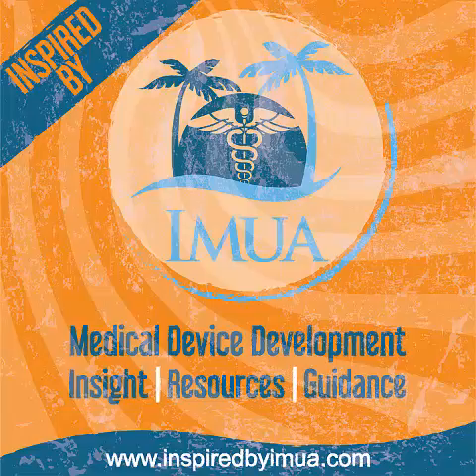So you might take some of the prototypes out to the field and get clinician feedback, right? How do they think it works? And then in a testing laboratory, how does this package perform when you put it through some hazards and stresses? Temperature, humidity, vibration, shock, drop. So that's probably the next phase of moving through a package development process.